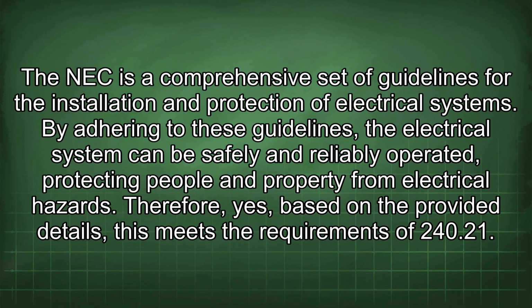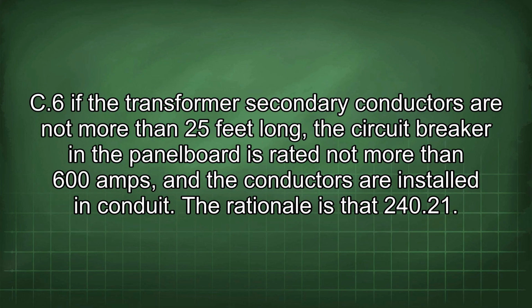Therefore, yes, based on the provided details, this meets the requirements of 240.21(C)(6), if the transformer secondary conductors are not more than 25 feet long, the circuit breaker in the panel board is rated not more than 600 amps, and the conductors are installed in conduit.